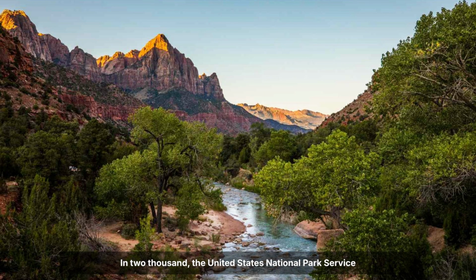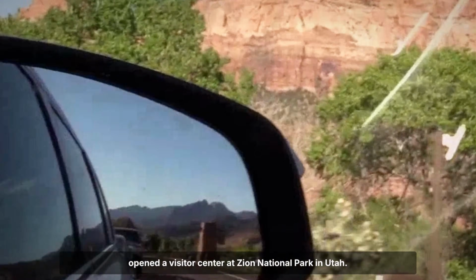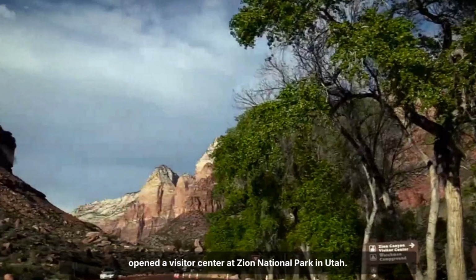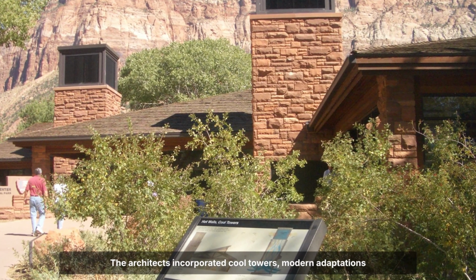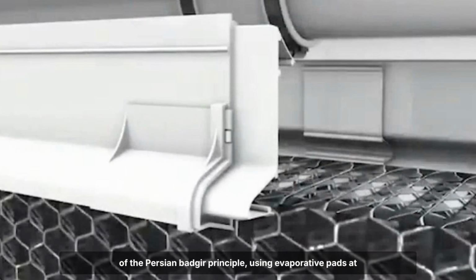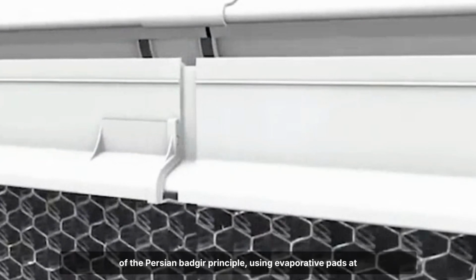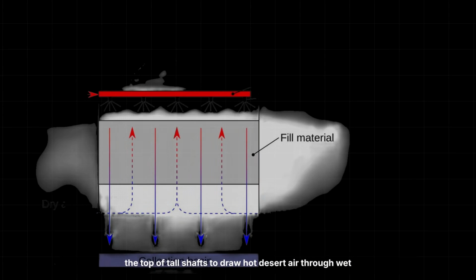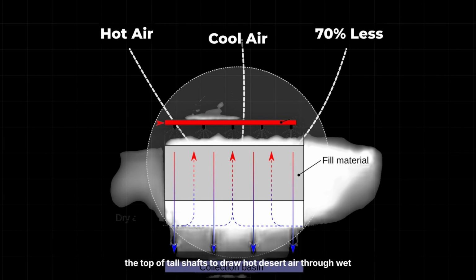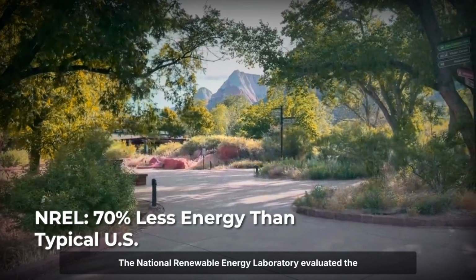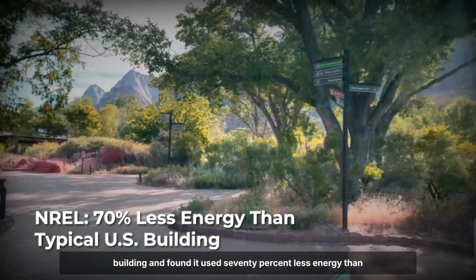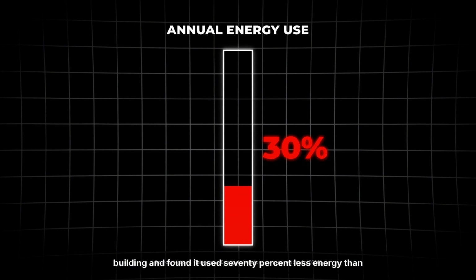In 2000, the United States National Park Service opened a visitor center at Zion National Park in Utah. The architects incorporated cool towers, modern adaptations of the Persian Badgir principle, using evaporative pads at the top of tall shafts to draw hot desert air through wet media and deliver cooled air to the interior below. The National Renewable Energy Laboratory evaluated the building and found it used 70% less energy than a comparable federal building constructed to the Federal Energy Code, 70%.